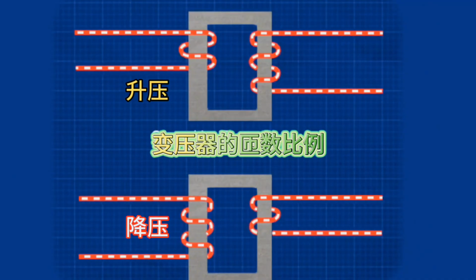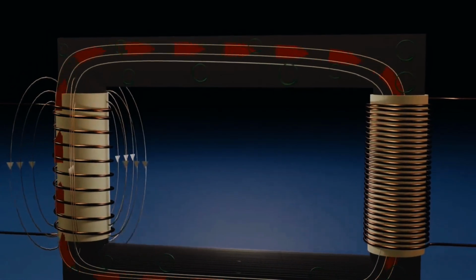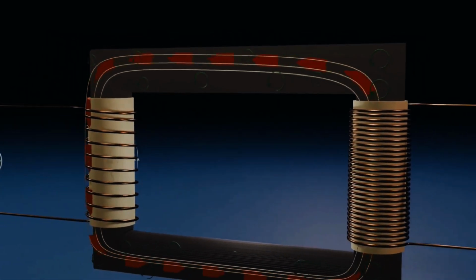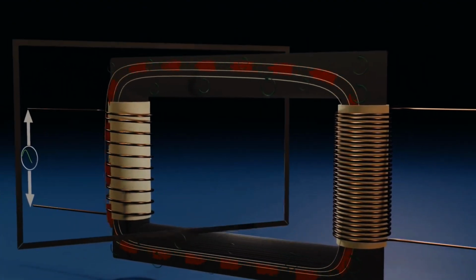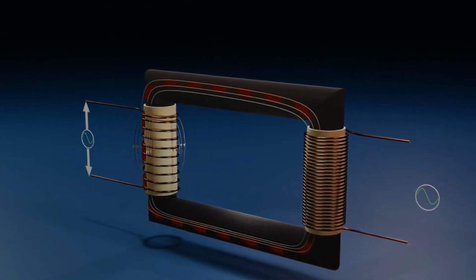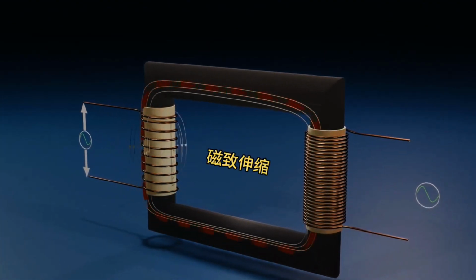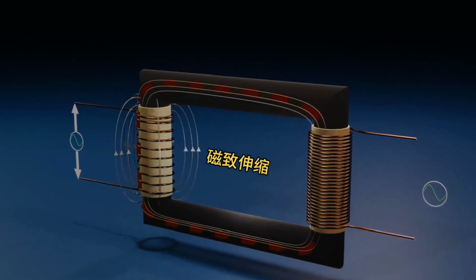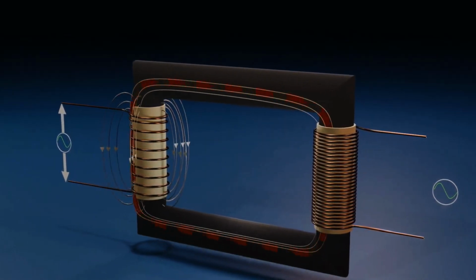So where does the buzzing sound from a transformer come from? It's because the transformer's core is made up of stacked silicon steel sheets. The repeated changes in the magnetic field cause magnetostriction, leading to the expansion and contraction of the transformer core, which results in the buzzing sound.